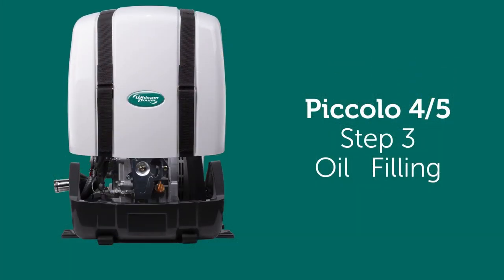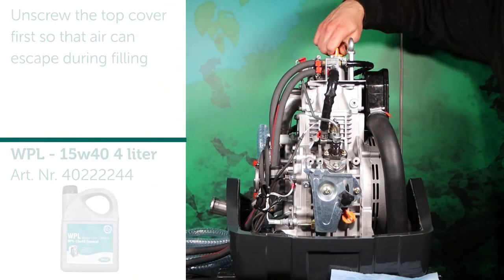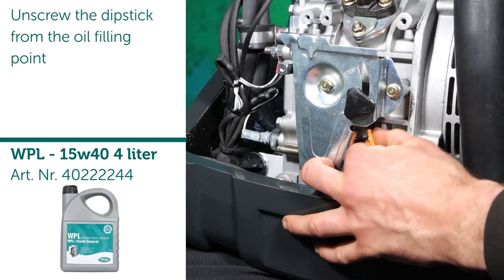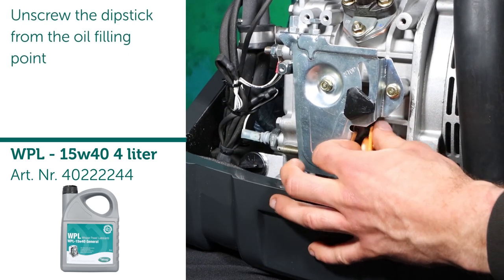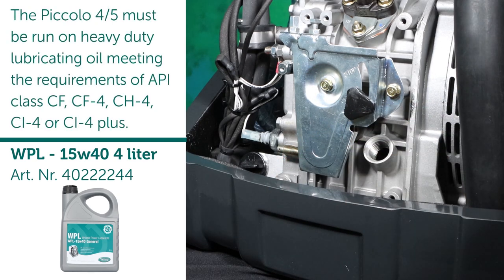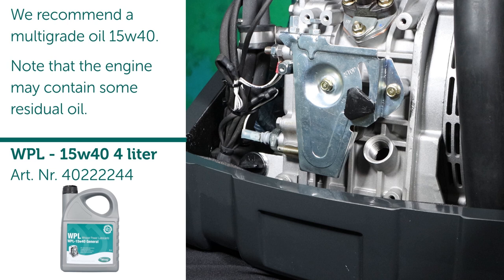Step 3: Oil filling. Unscrew the top cover first, so that air can escape during filling. Unscrew the dipstick from the oil filling point. The Piccolo 4-5 must be run on heavy-duty lubricating oil, meeting the requirements of API Class CF, CF4, CH4, CI4 or CI4 Plus. We recommend a multi-grade oil 15W40.